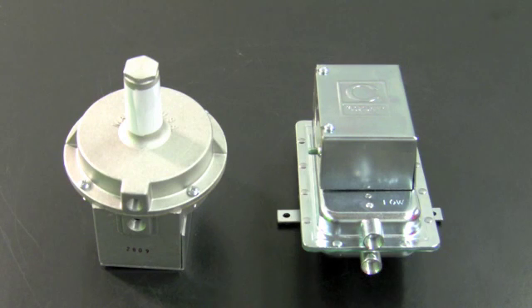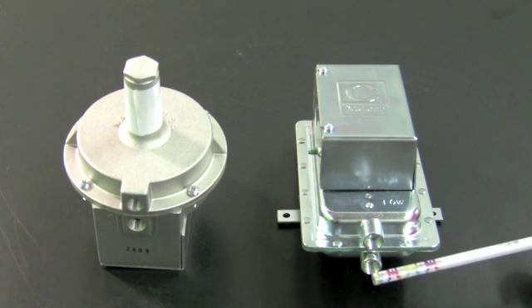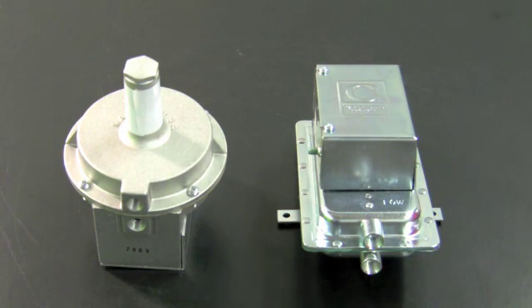If we're hooking them up differentially, we go from the low side before the fan, the high side to after the fan, and we're good to go. You hook it up that way, set your pressure, you're in and out in no time.